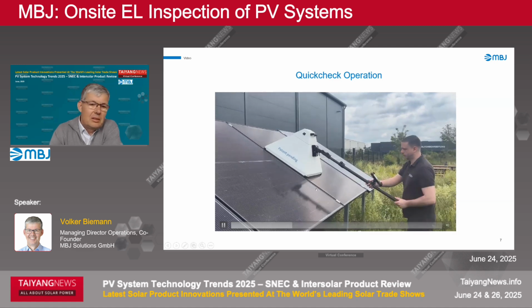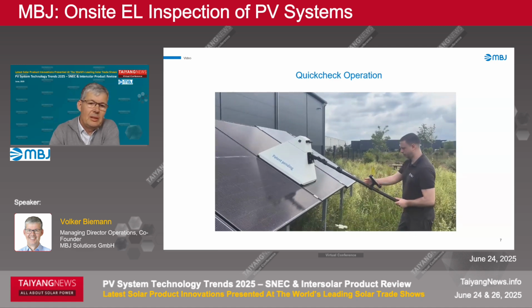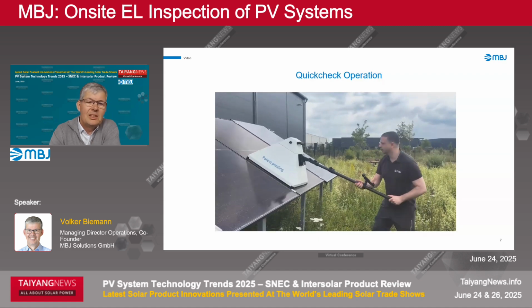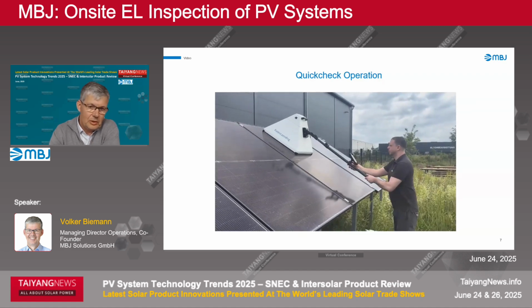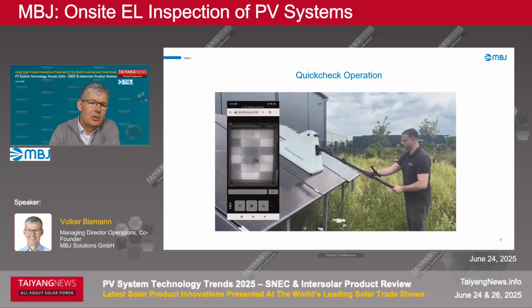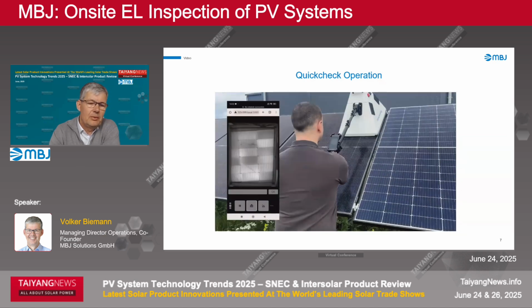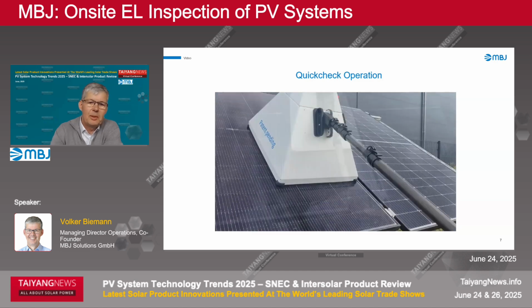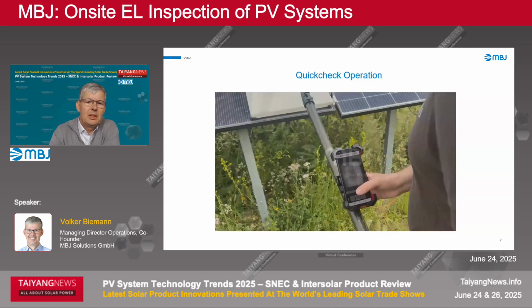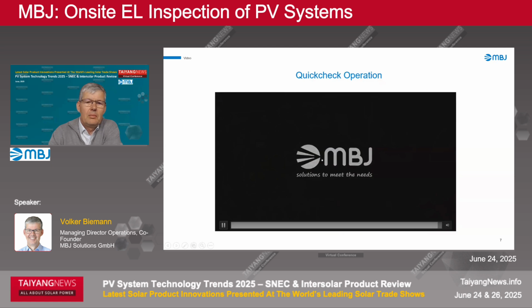You slide the head on the surface of the module, and every time it touches, the smartphone stores the luminescence image. So to capture the full image, you have to go position by position on the module and store the images. If you're just looking for cracks, you can also move it over the solar panel without stopping and storing each image—you just stop where you can see defects.